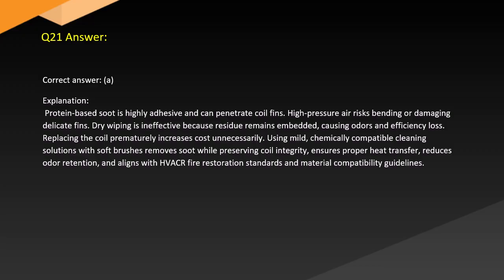Answer. Correct answer: A. Explanation: Protein-based soot is highly adhesive and can penetrate coil fins. High-pressure air risks bending or damaging delicate fins. Dry wiping is ineffective because residue remains embedded, causing odors and efficiency loss. Replacing the coil prematurely increases cost unnecessarily. Using mild, chemically compatible cleaning solutions with soft brushes removes soot while preserving coil integrity, ensures proper heat transfer, reduces odor retention, and aligns with HVACR fire restoration standards and material compatibility guidelines.